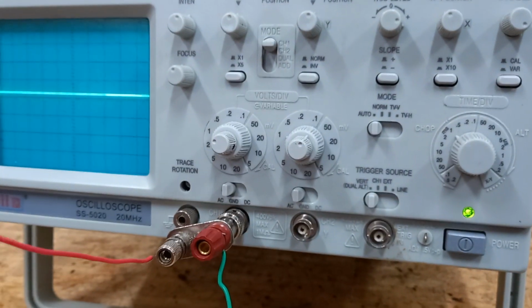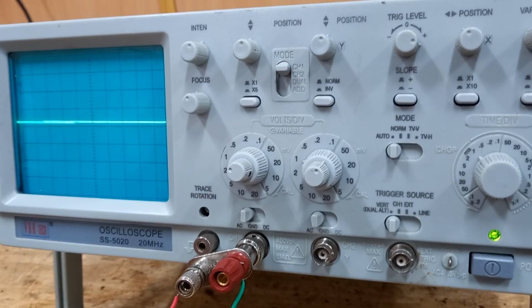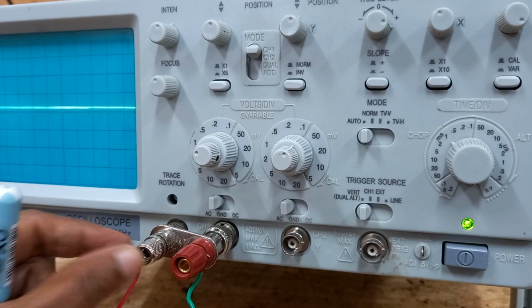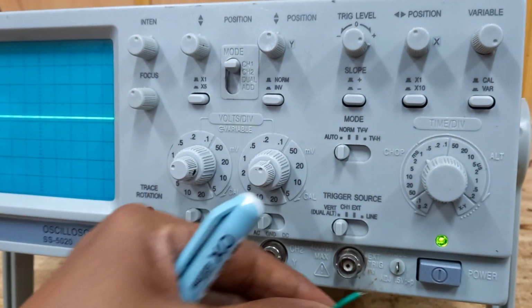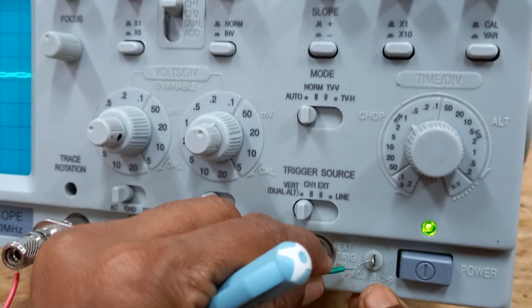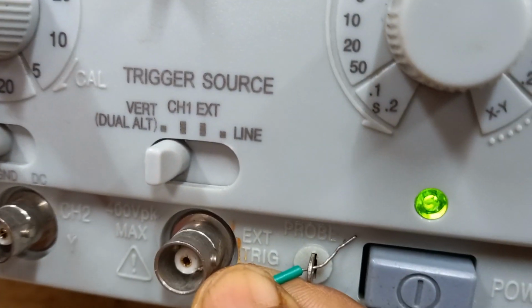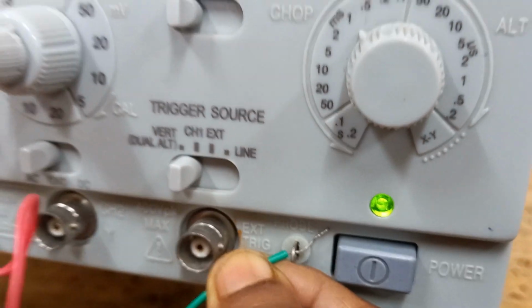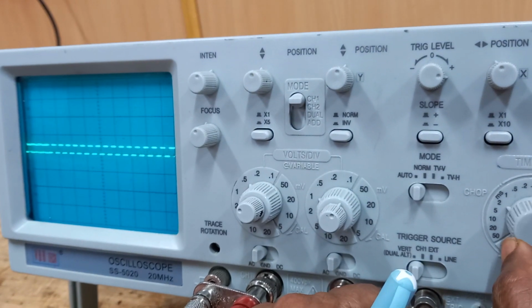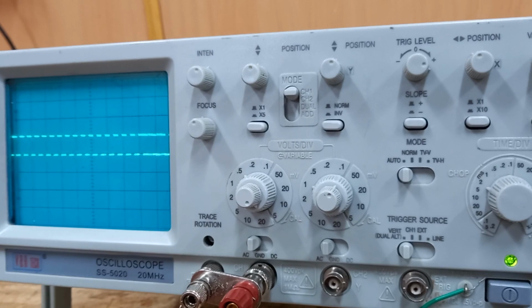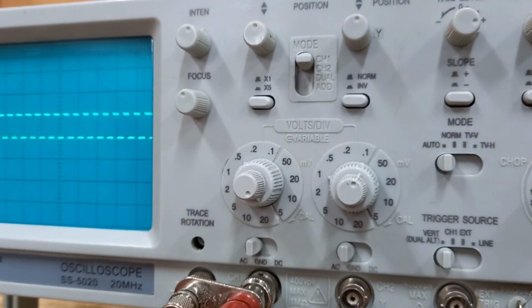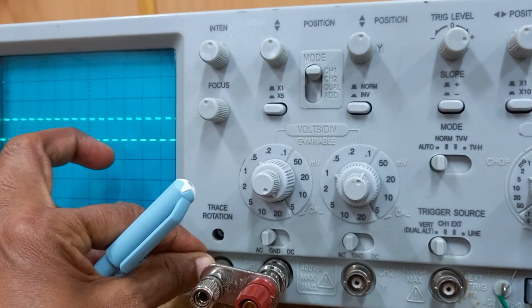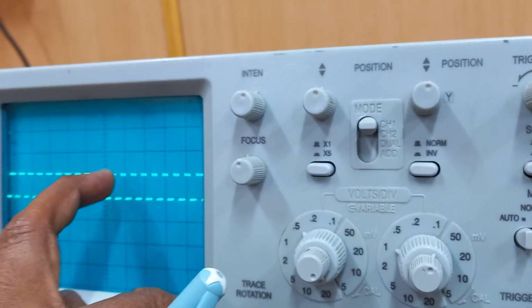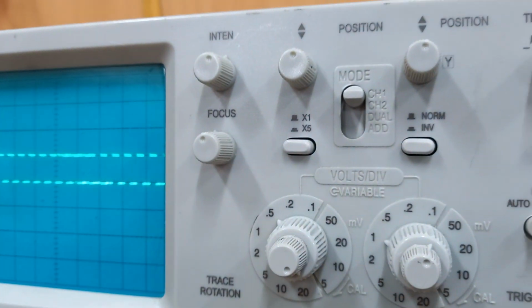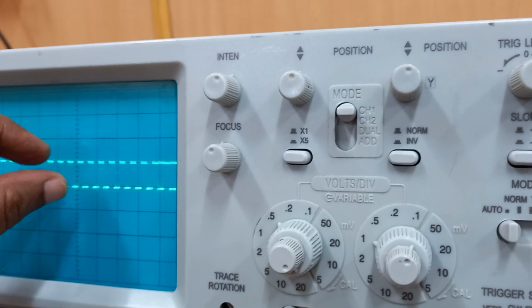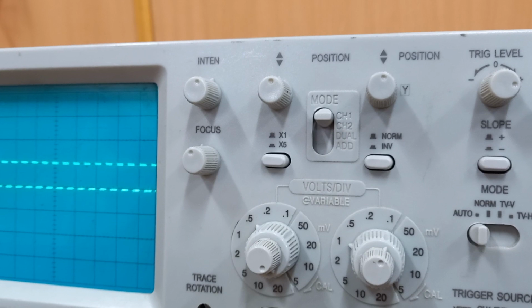Now I will show you how to check whether the CRO probe is in good condition or working. See, here I have connected the T connector, this is positive and this is ground. The positive of the CRO probe or the T connector you connect to the 0.5 volts peak to peak adjustment. Here there is one notch, you connect here. As soon as I connect to the 0.5 volts adjustment and negative to ground, I get this square waveform. Count the divisions, it has completely covered 1 unit. So 1 unit into 0.5, how much am I getting? It is 0.5 volts. If I am getting such a waveform, then we say that the CRO probe is in working condition.